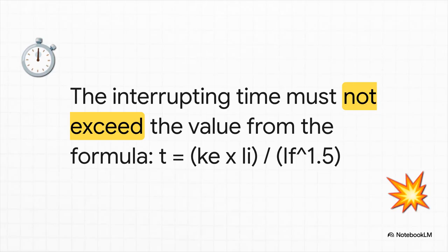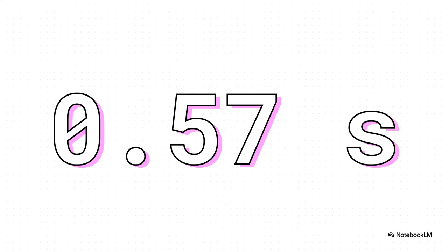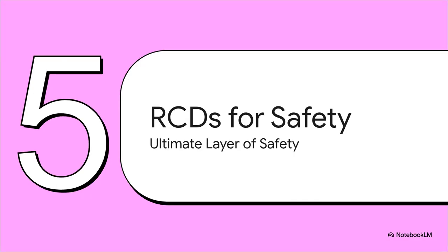To make sure that protection is fast enough, the standard gives us this very formula. It's a way to calculate the absolute maximum time the device can take to clear the fault. The whole idea is to cut the power before the arc's energy release gets to a point of no return. Okay, let's make that formula real. Say we have a pretty standard 800 amp main switchboard. We run the numbers, and we figure out that if there's an arcing fault, the main breaker has to shut everything down in less than 0.57 seconds, just over half a second. That's it. Any longer than that, and the energy released is so massive that it could cause a catastrophic failure of the entire switchboard.